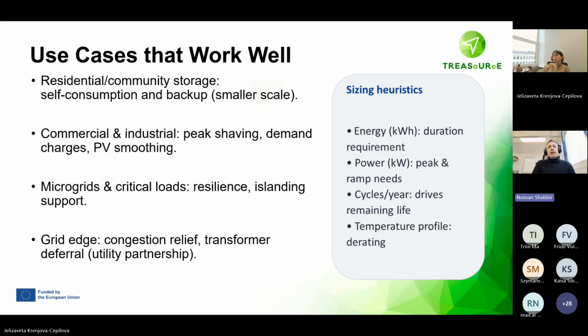These kinds of large battery banks can provide resilience in emergencies - you can use energy from these battery banks. Then there's grid edge congestion relief - for example, if there's excessive PV that causes congestion in the system, system operators usually use PV curtailment or energy curtailment, lowering PV generation from 100% to 50% or 30%, and the rest of the energy is just wasted. This storage can be used for congestion relief instead.